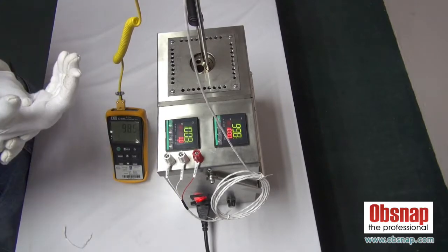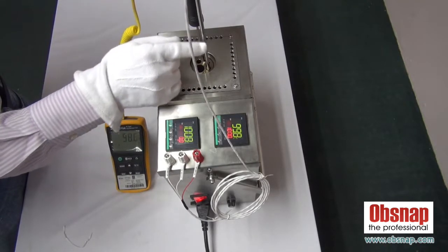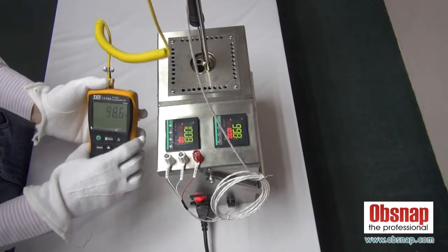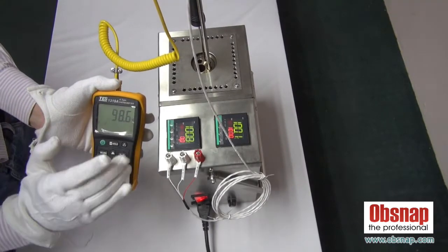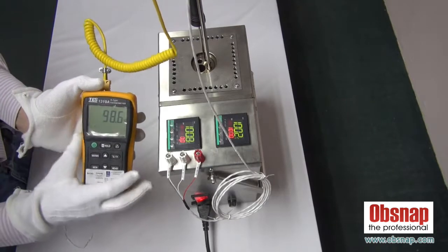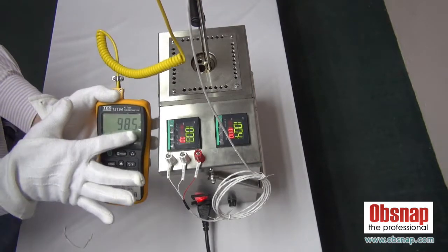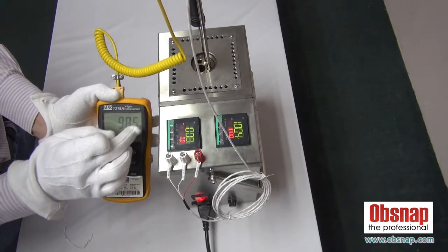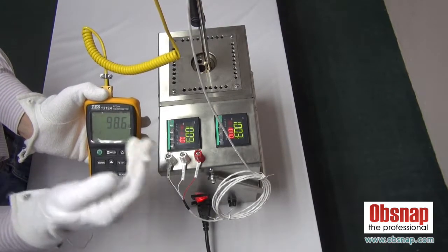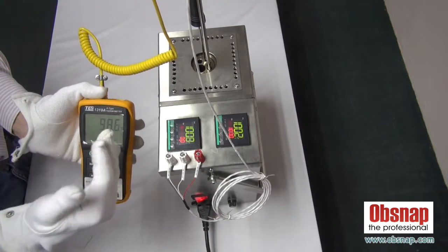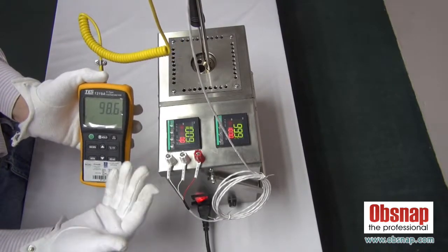How to judge that the temperature is ready to use? It's very easy. By comparing the reality and the reference. As you can see, when they are consistently increasing and consistently reducing - that's the time we can take up the reading. However, for this case, we can't see much difference because this indicator only has 0.1 degrees. What I mean is it's talking about the 2 decimal or 3 decimal point behind. Then you will very obviously see the temperature will be increased and decreased. So for this case, we can start taking reading.